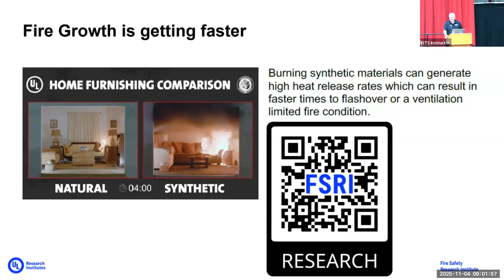So what's the change? It's in the chemistry of the material itself, the heat of combustion, the amount of energy it can release when burning. For wood, we're releasing 12 to 15 megajoules per kilogram. Polyurethanes can be anywhere from 20 to 30 megajoules of energy per kilogram. And gasoline, typically we use a number of 43.7 megajoules per kilogram.